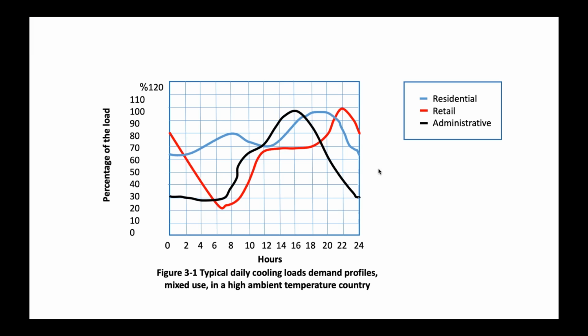Now, what is diversity of use? District cooling becomes very competitive and economical if you've got several applications needing cooling at the same time, or in the same district. For instance, look at this graph, a typical daily cooling load demand profile for several applications. The black curve is the administration application, where cooling is more needed towards late afternoon, when everybody is back in place and the sun is shining and heat is at its utmost.